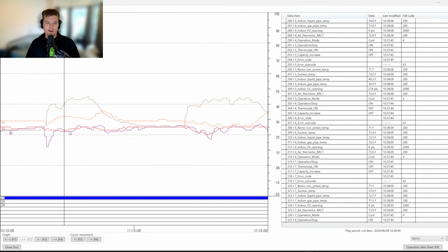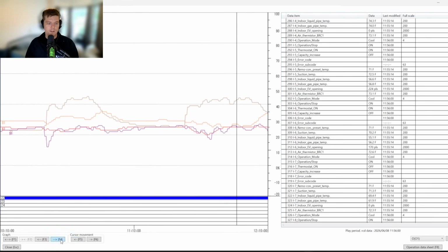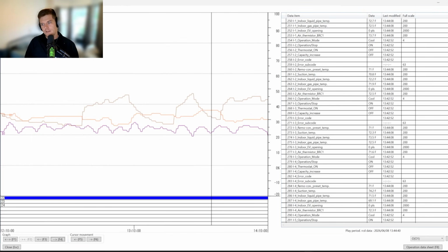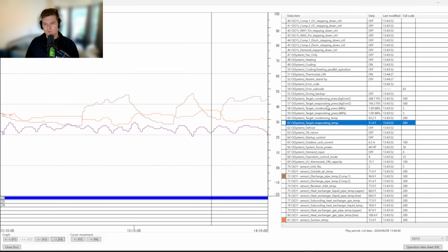And you can see here between all the data, it kind of levels out eventually. And obviously compressor speed dictates that. You can see where it probably turned off, compressor discharge goes down, and then it goes back up again here. So if I keep going through the data, you can see that. See the squiggly wigglies here? Yeah, that's a scientific term in case you're wondering. Those are all consistent with what's going on in the system. And so if I want to go back and take this away, you'll notice that the valves are at low pulses, the demand in this building is really low.